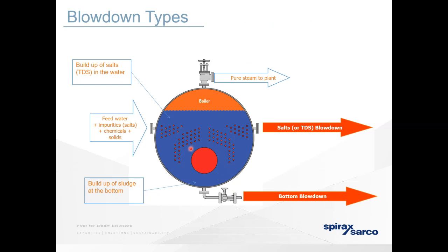So how a boiler goes critical is usually because of bad TDS, bad water quality, and bad blowdown. What you find is you get a crustation on the fire tube. A scale actually has a higher melting temperature than the steel the boiler is made out of, but it also reflects heat back into the tube rather than allowing it to be conducted into the water around it.